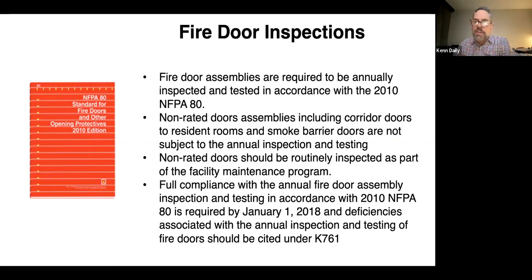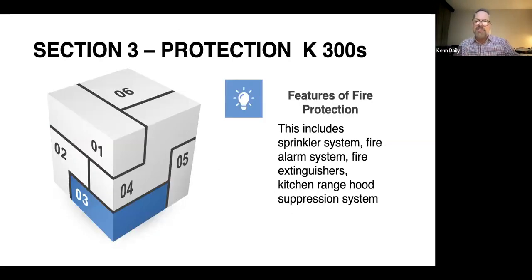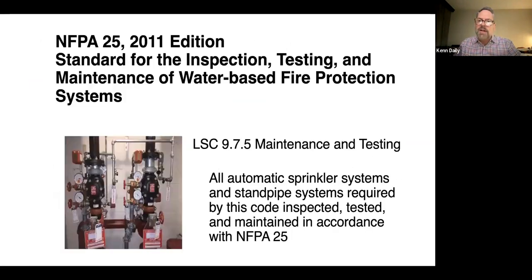It's a tool that you would use to inspect each door. And then the most important aspect is that you find all these doors in your building. I mean, you have to locate the doors in your building that are fire rated doors, and then you inspect those doors based on the annual inspection criteria. Moving to the 300 series, the most basic is going to be the inspection, testing, and maintenance of your sprinkler system. All that ITM is done under NFPA 25.